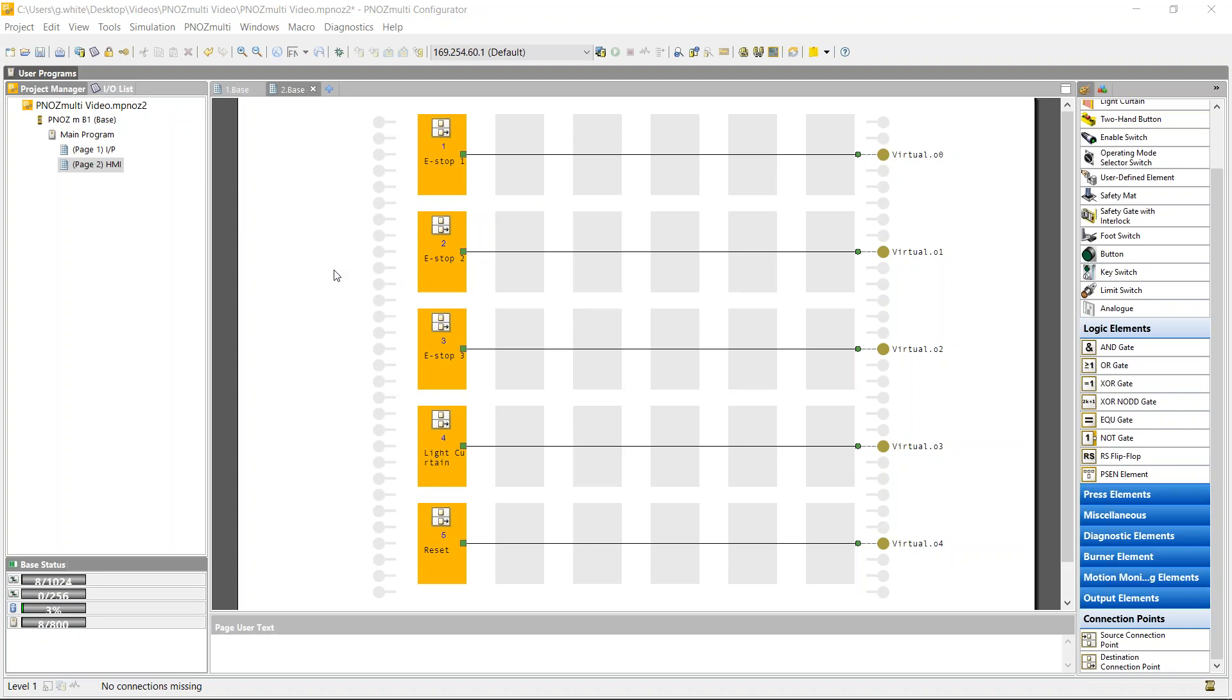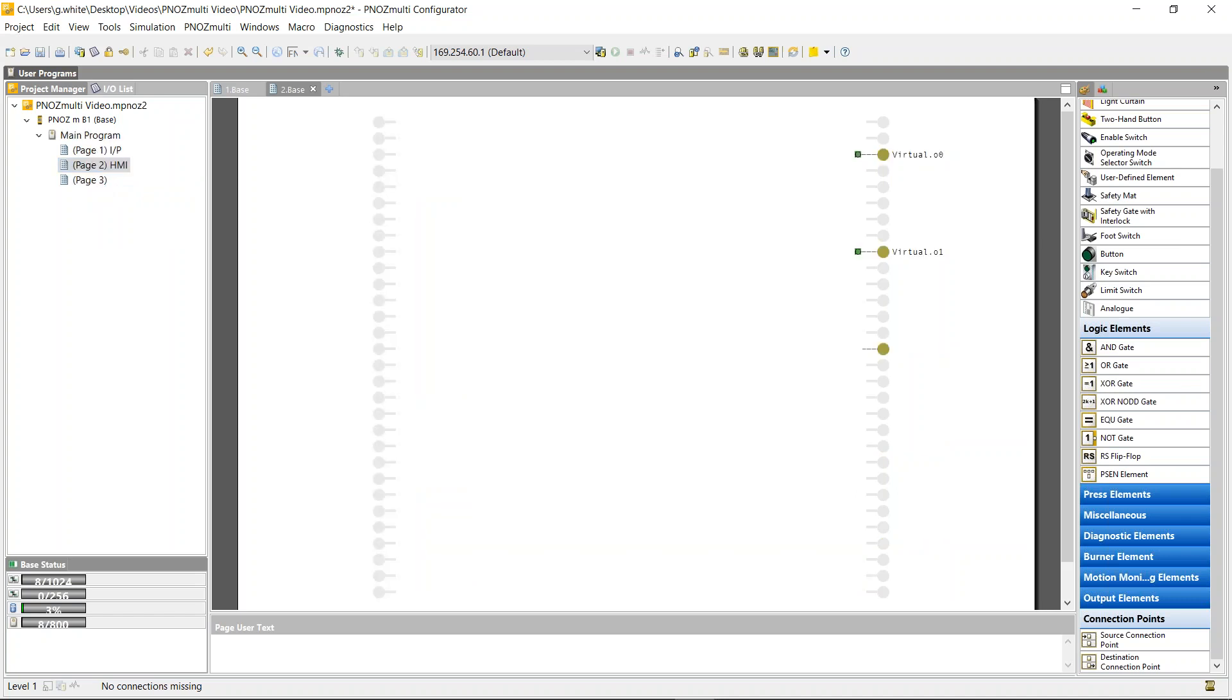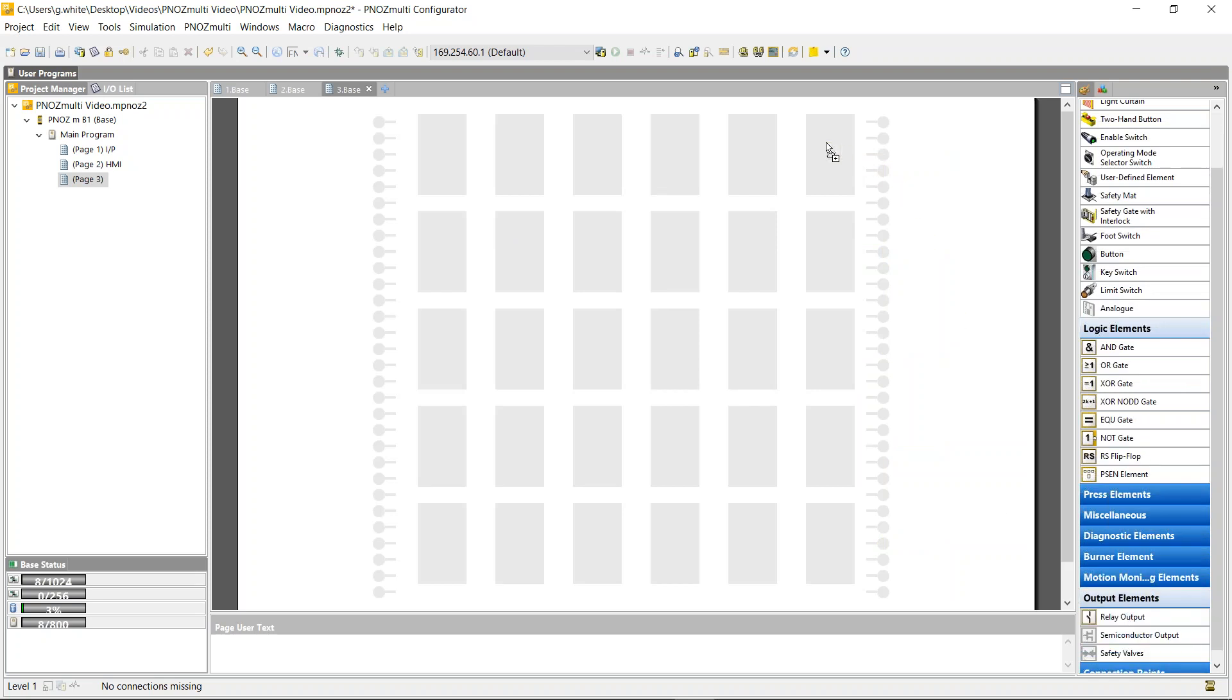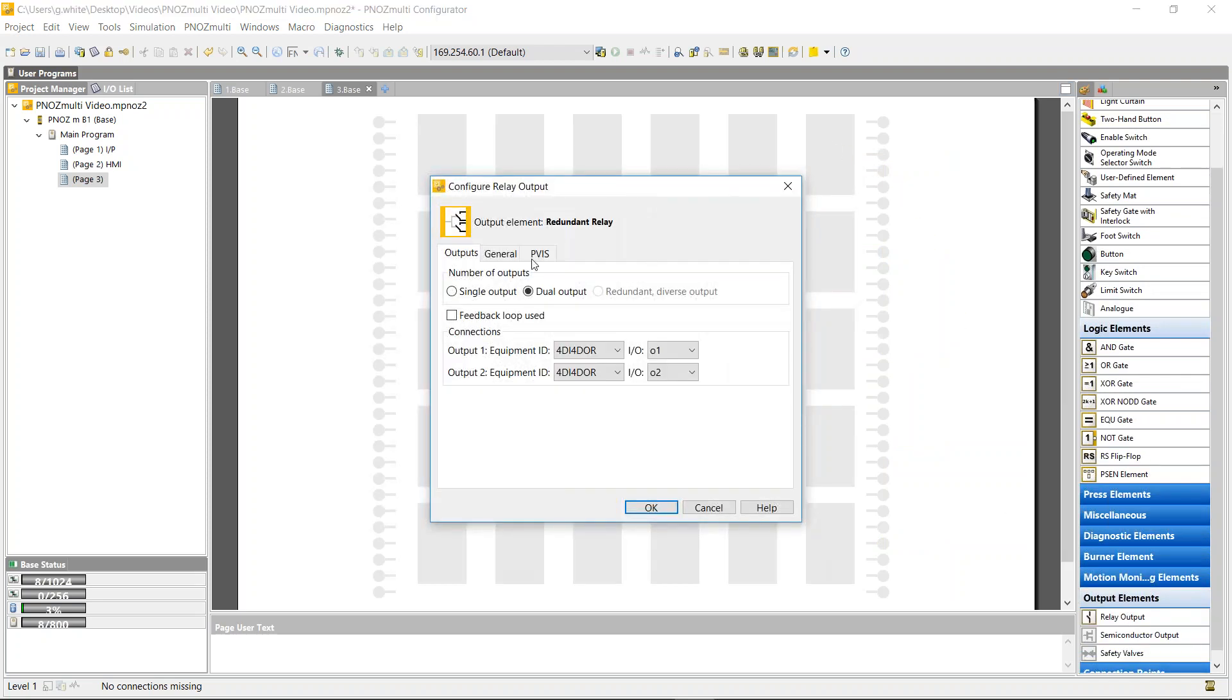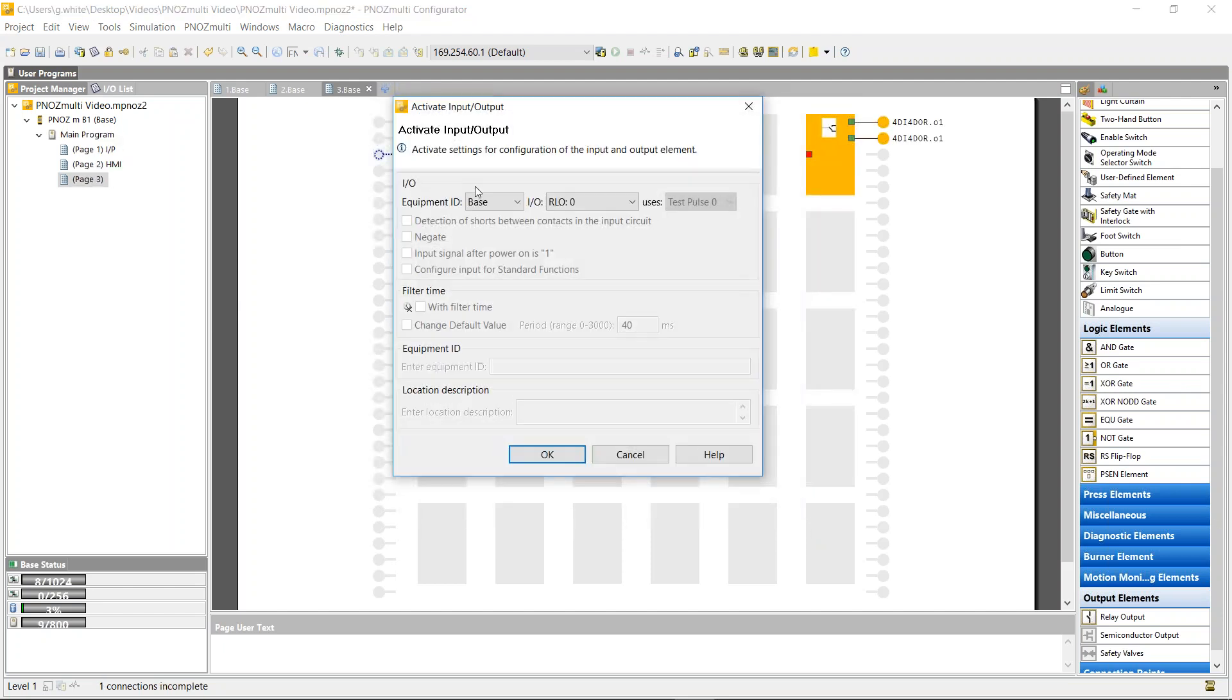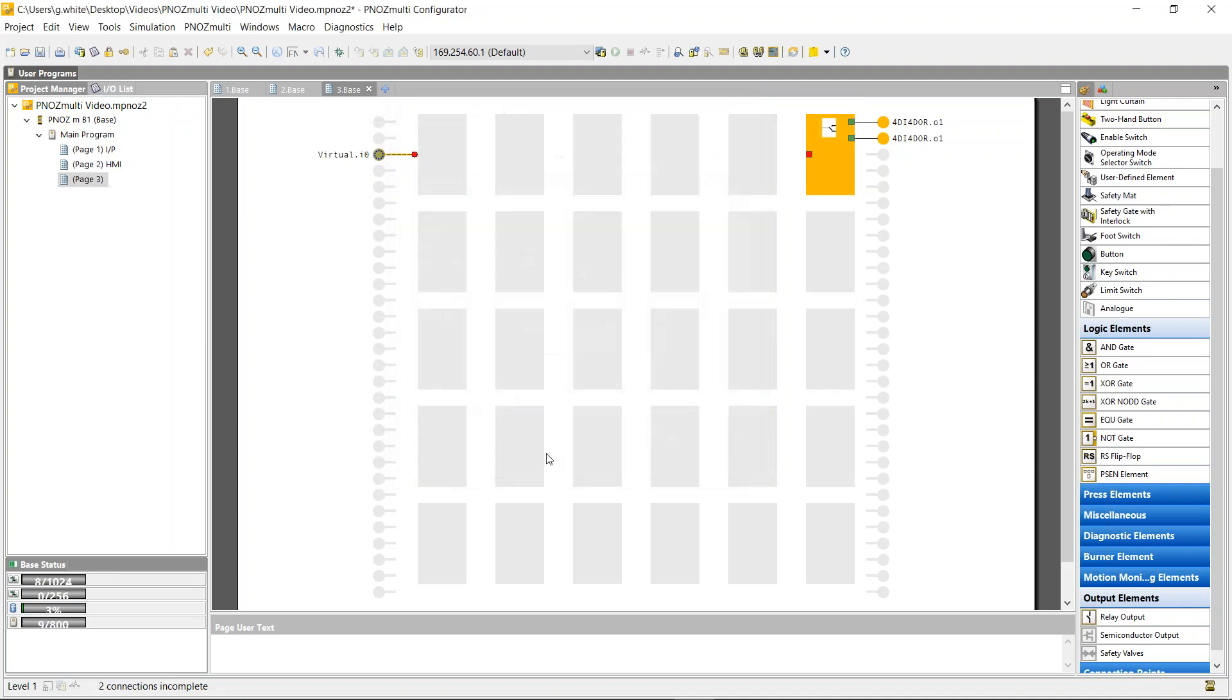But if I wanted to send from the HMI to the PNOZmulti, I can do that quite easily, but I'd have to use a safety function as well. So if I wanted to turn on an output via a push button on the HMI screen, that's using a standard function to a safety output, which can't be done. So from the virtual IO, I can't use an input because that's a standard function. So it won't let me drag and drop it here.